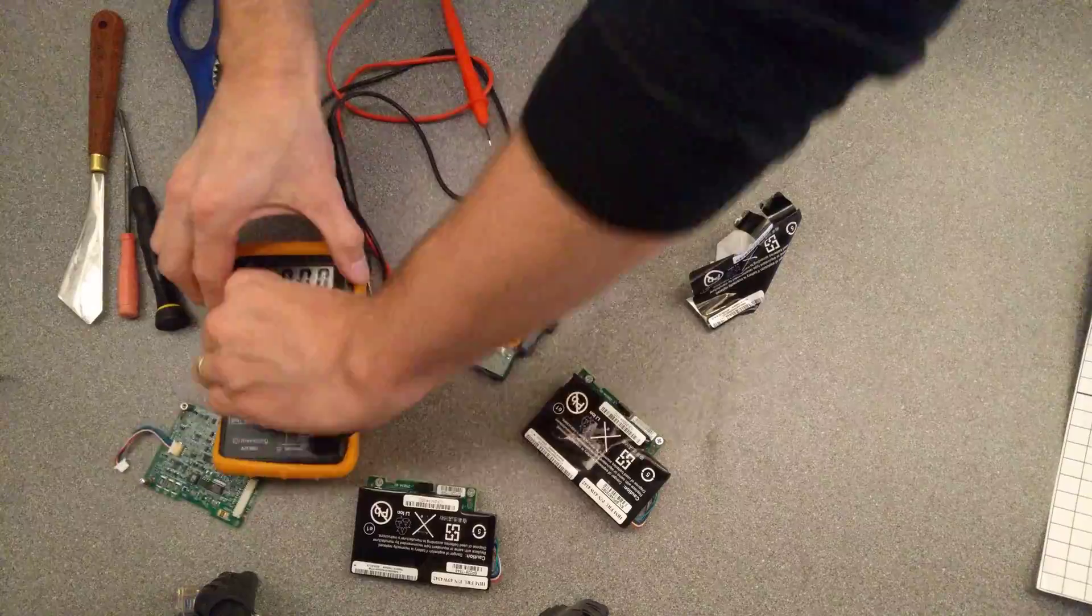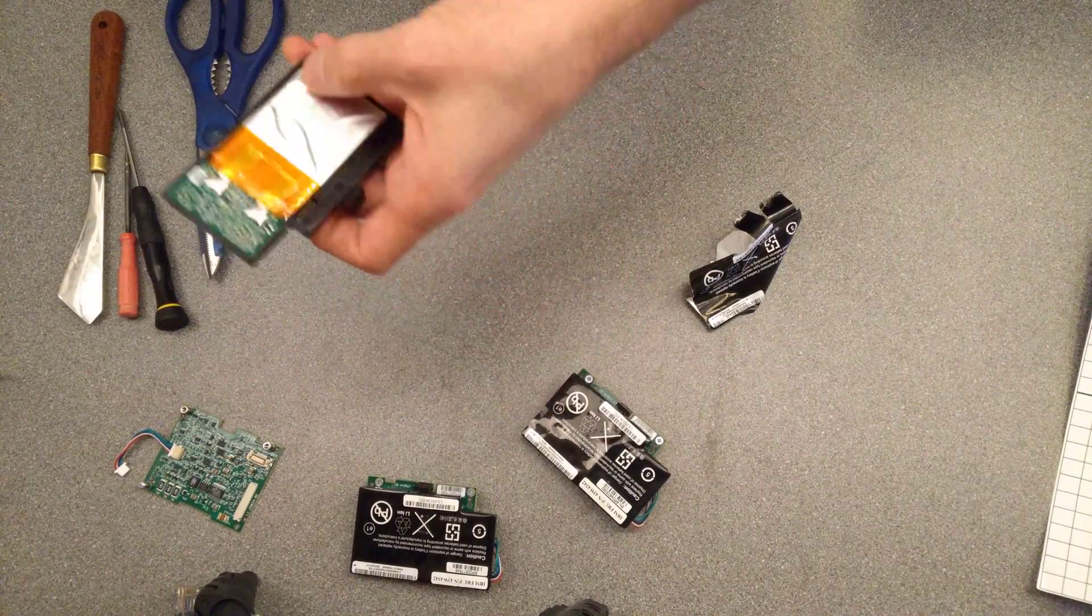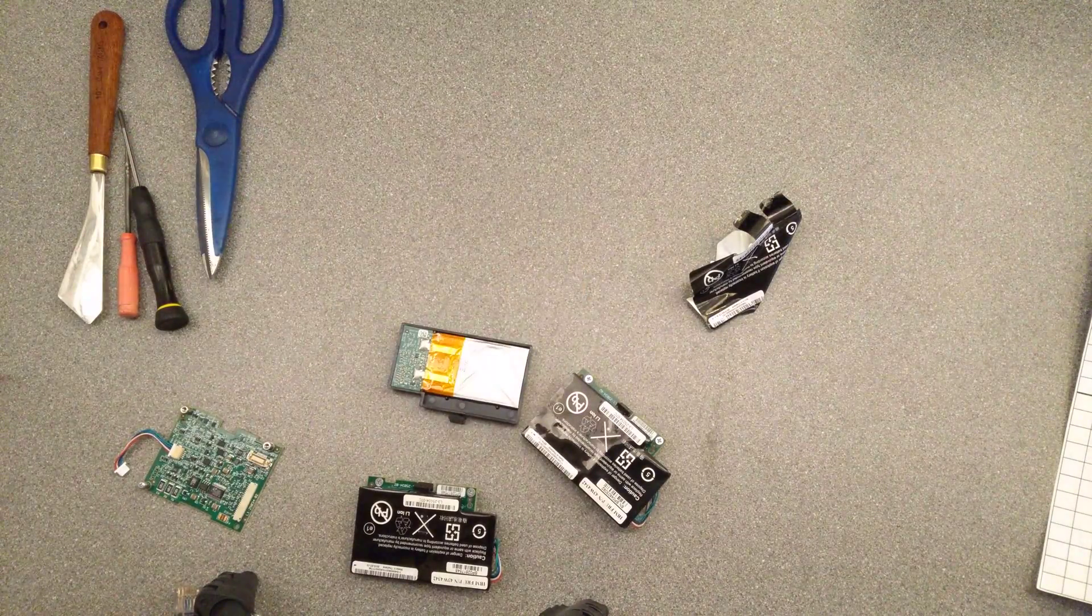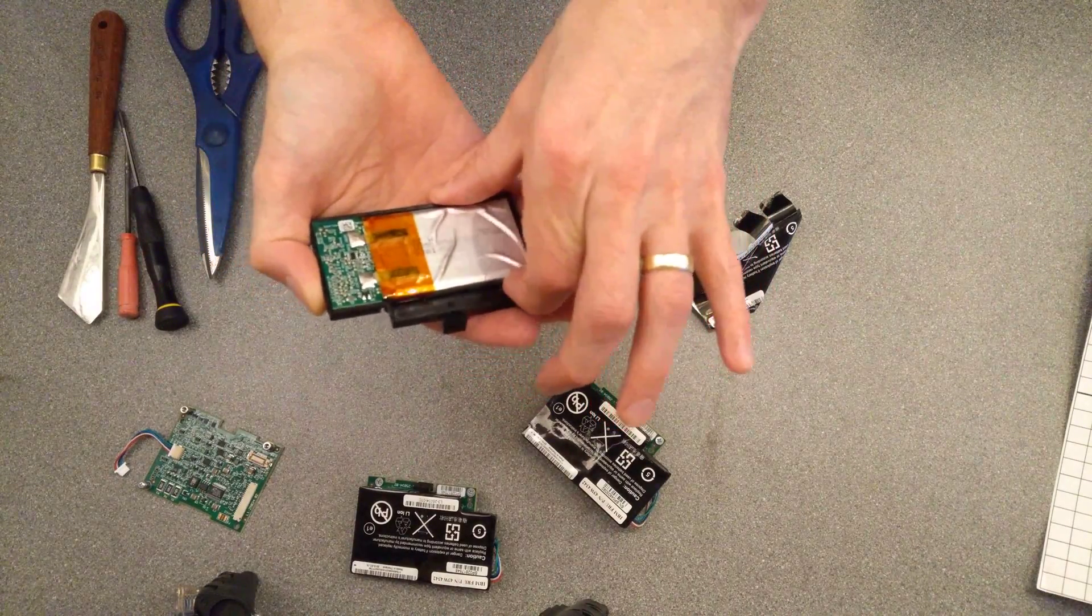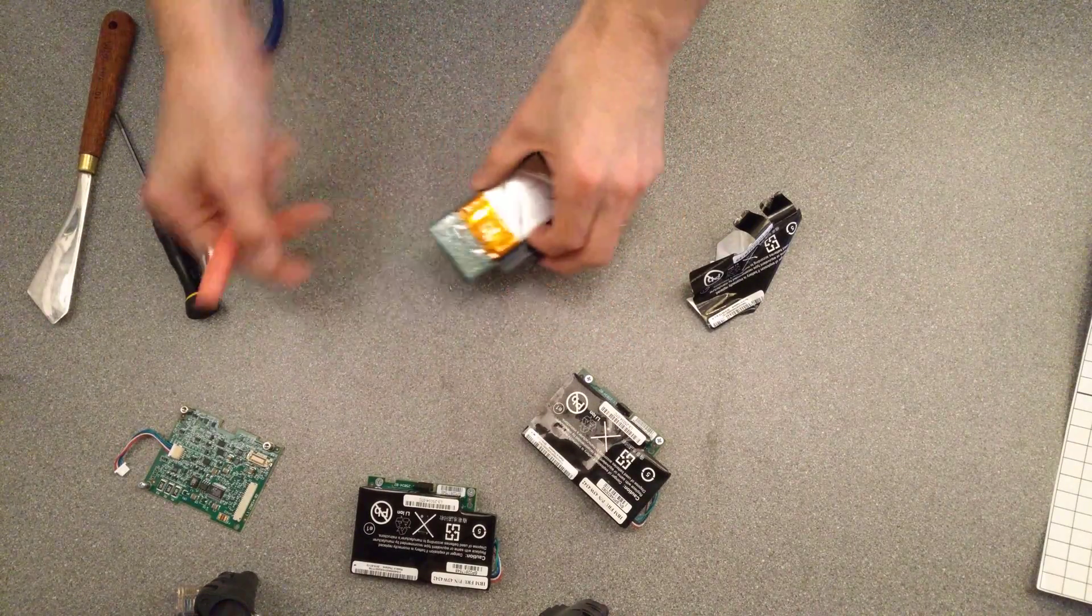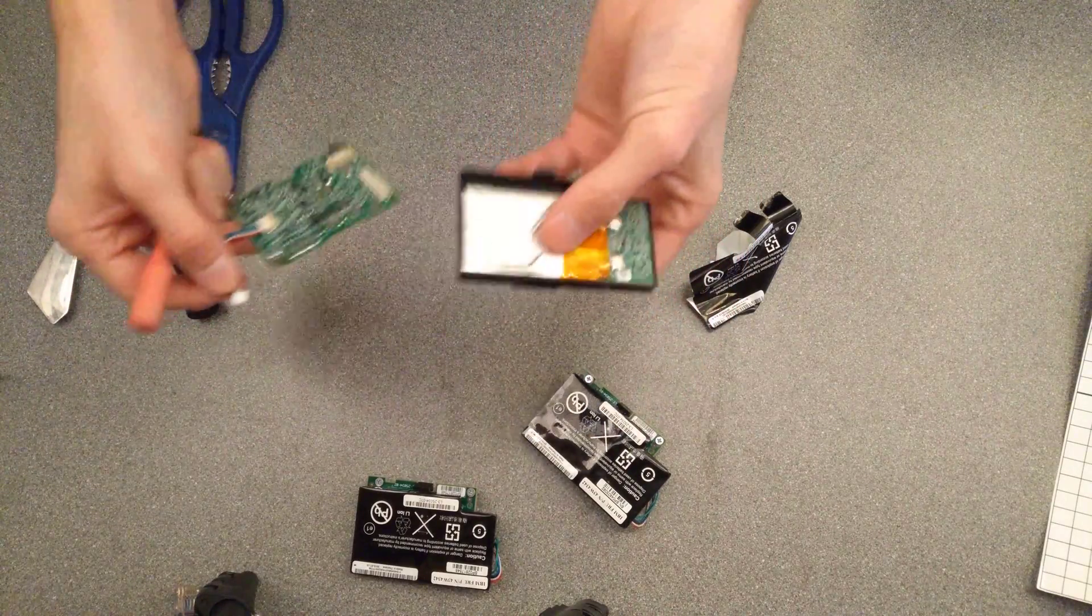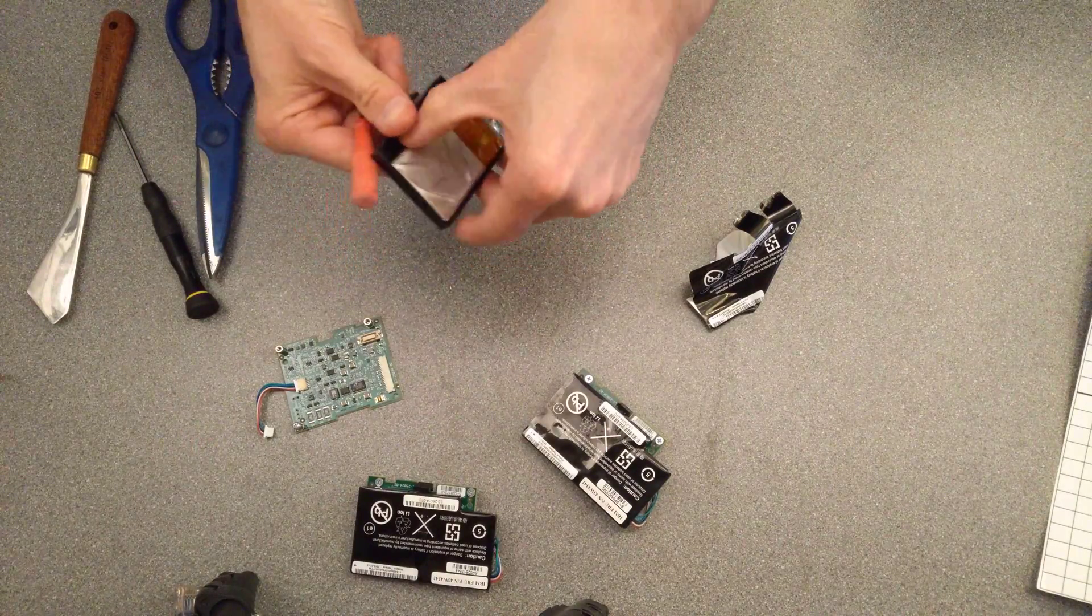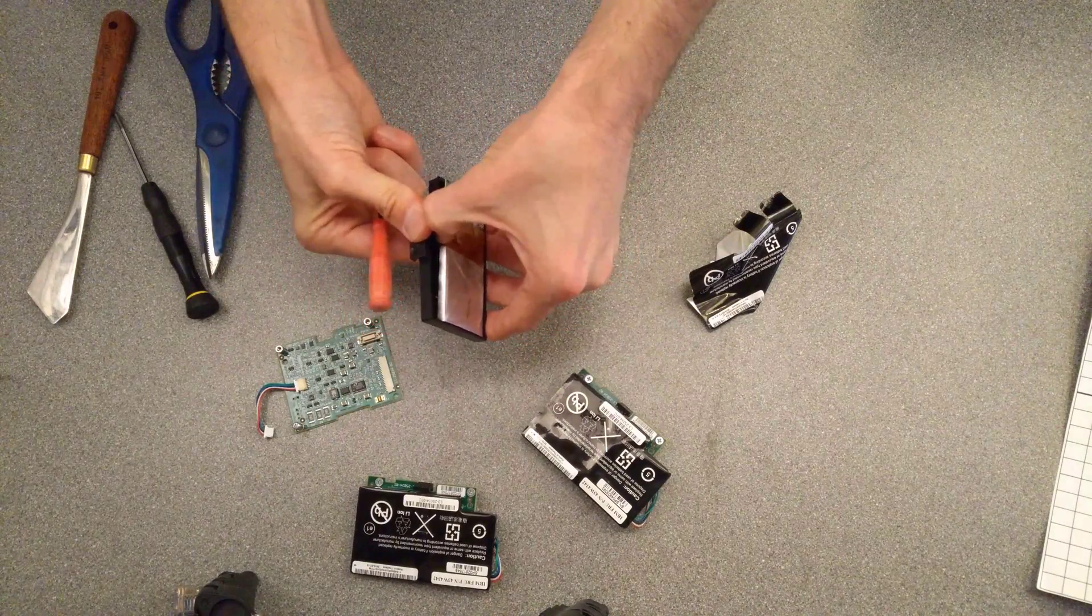The RAID cards would sit there and make the battery warm. As I say, in the case of one of these, the battery would actually puff up. Even a day later, you'd reboot the server and it wouldn't detect the battery and just say no battery was present. You take another battery and plug it in and it's fine, so it's not the controller cards. It's just end of life batteries.